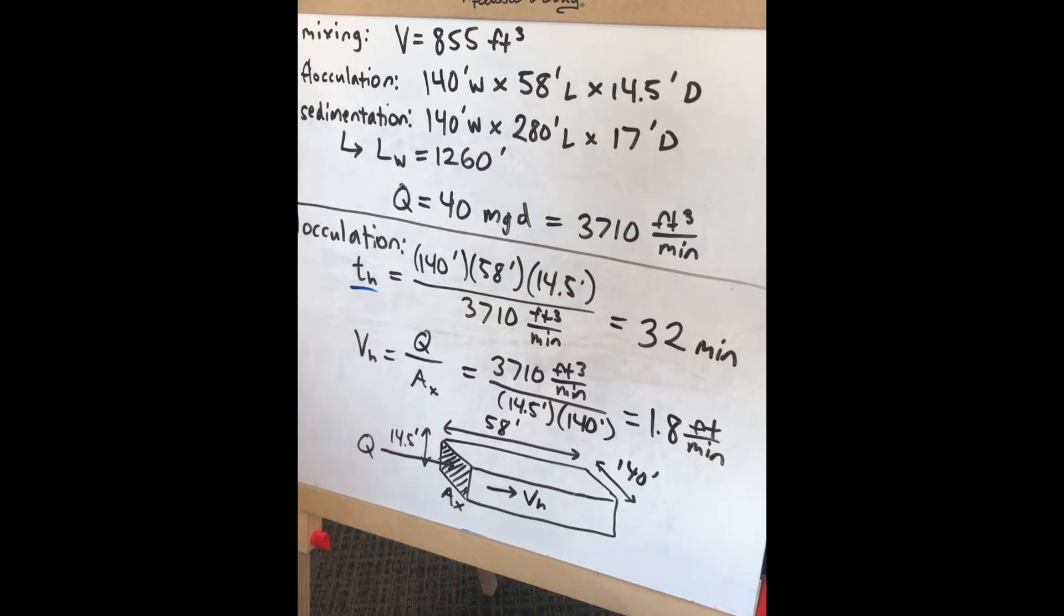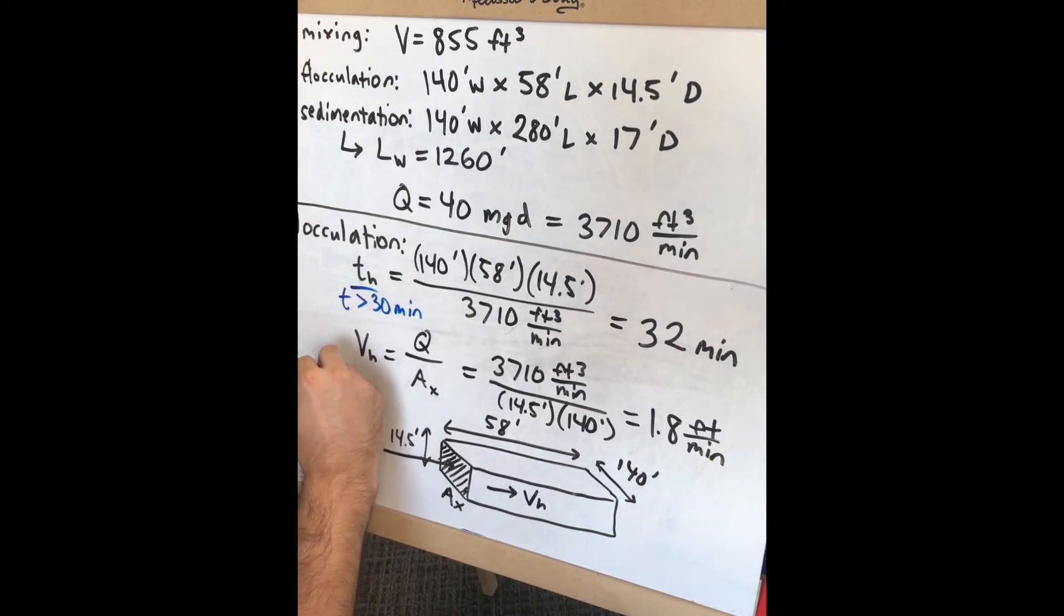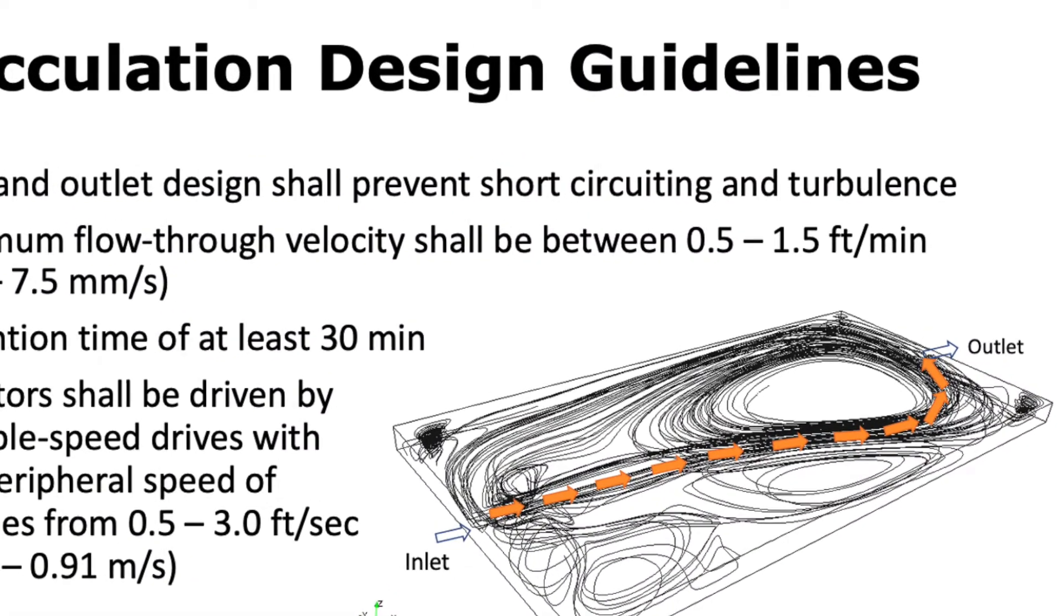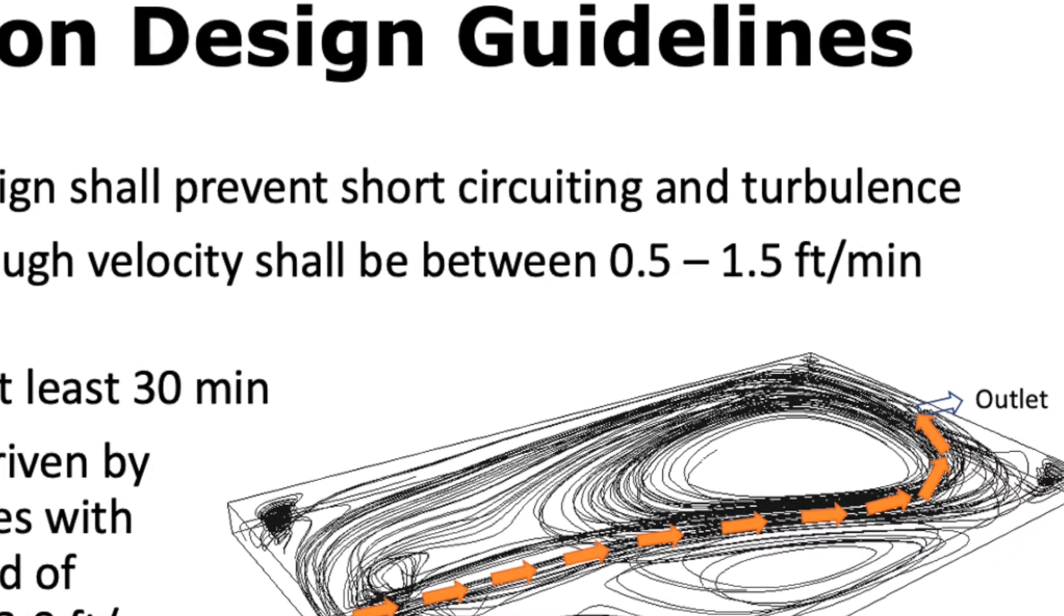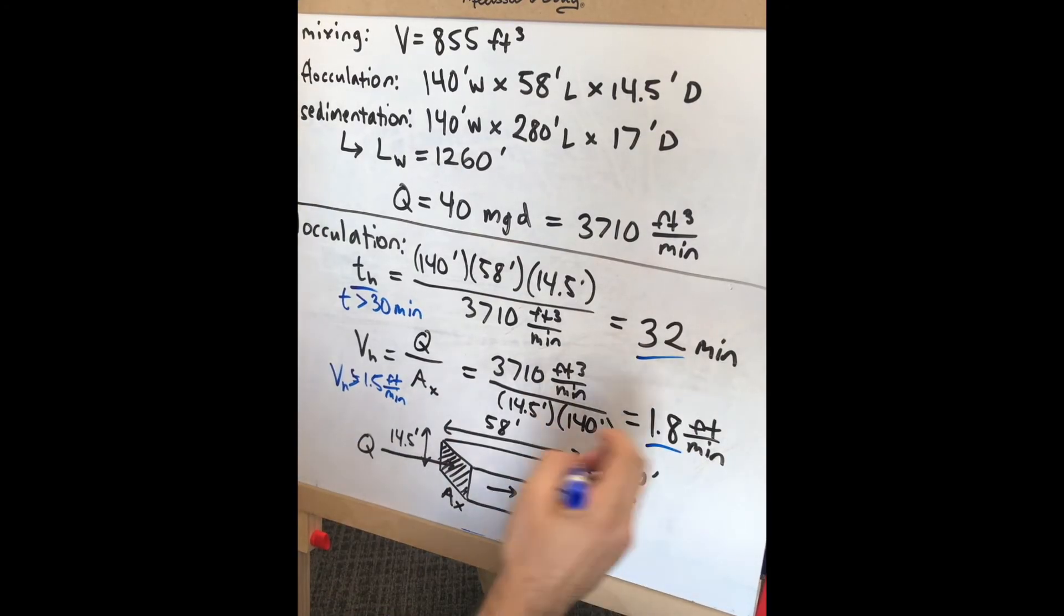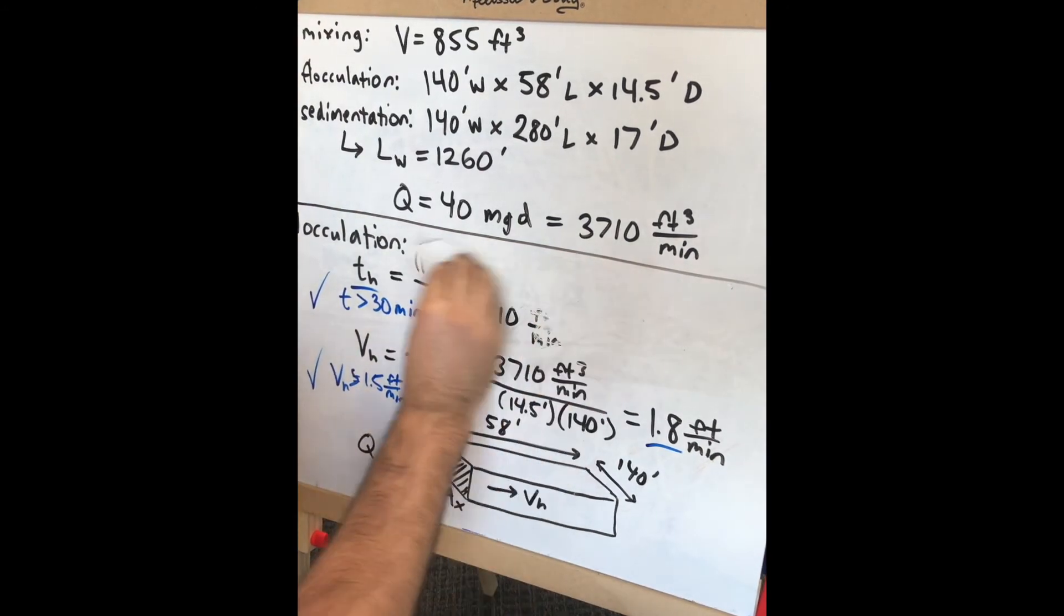The design criteria specify retention time should exceed 30 minutes and horizontal flow velocity should be between 0.5 and 1.5 feet per minute. Our retention time is acceptable, but the horizontal flow velocity of 1.8 feet per minute is too fast.